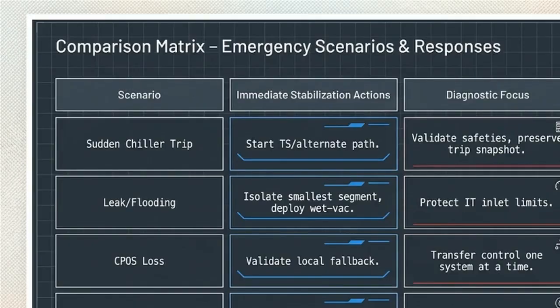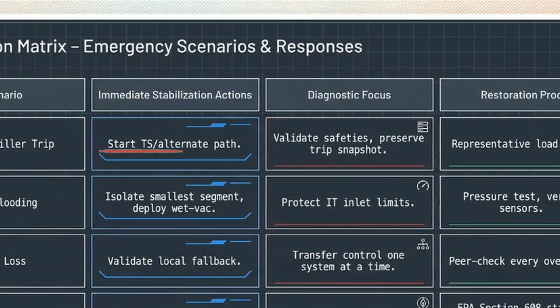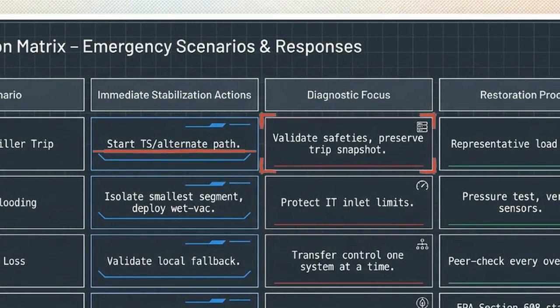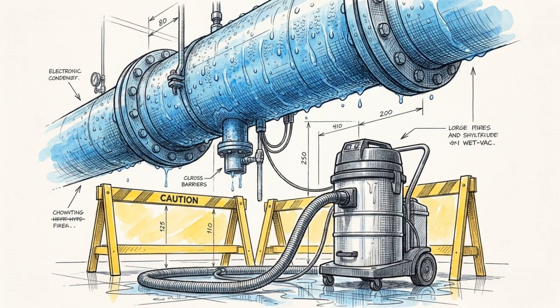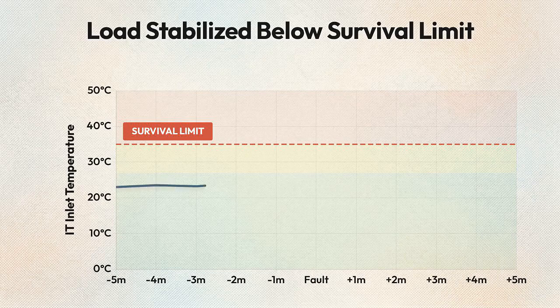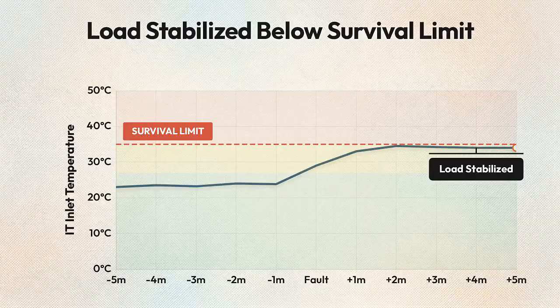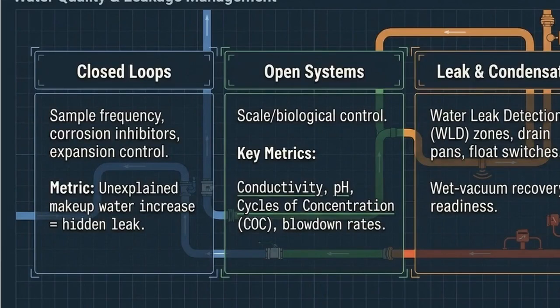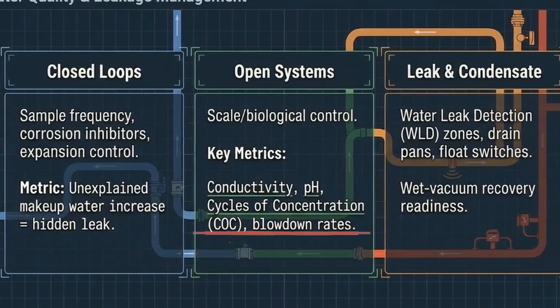For a sudden chiller trip, operators instantly start alternate paths, validate the hardware safeties, and preserve the digital trip snapshot before touching the physical unit. In the event of a hydronic leak, the protocol is to isolate the smallest possible pipe segment and deploy wet vacs. The overarching diagnostic focus remains strictly on protecting the IT inlet temperature limits above all else. To prevent leaks entirely, operators monitor closed loops for unexplained makeup water increases and carefully track cycles of concentration and blowdown rates in open systems.